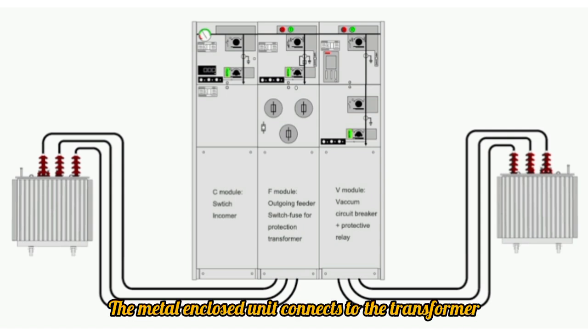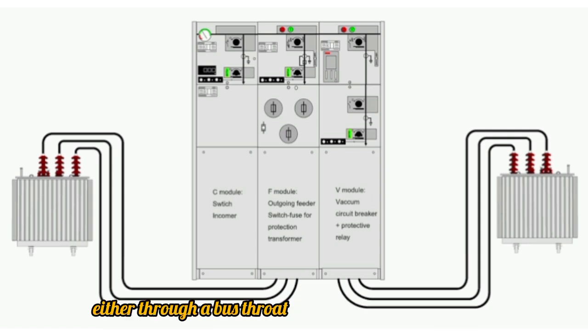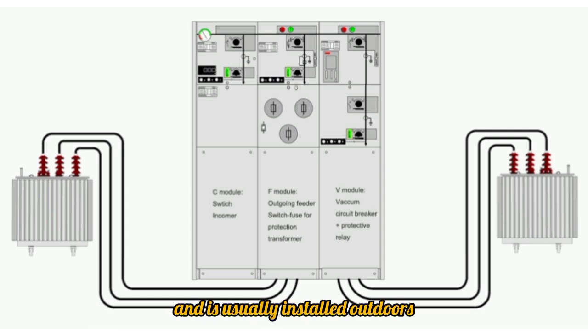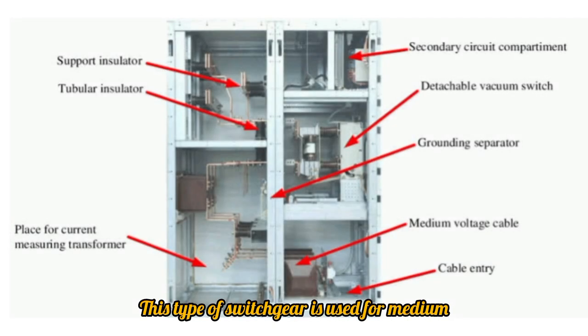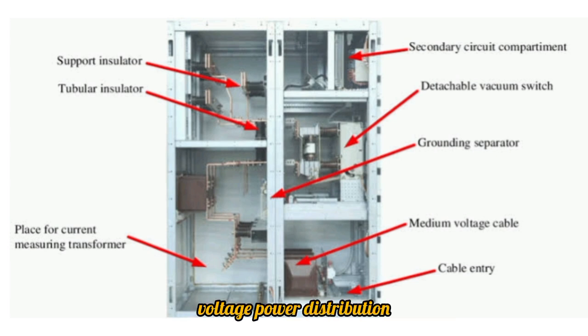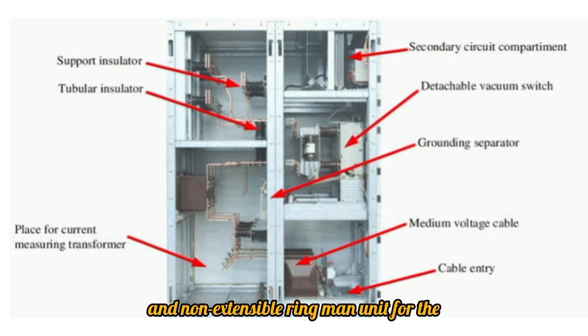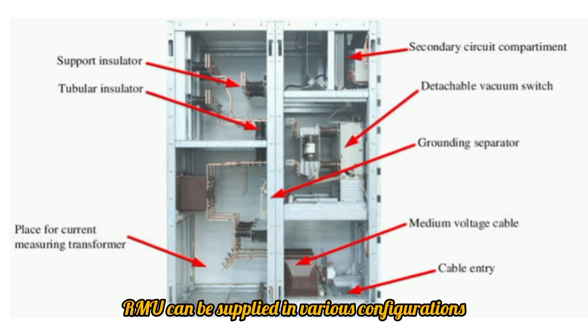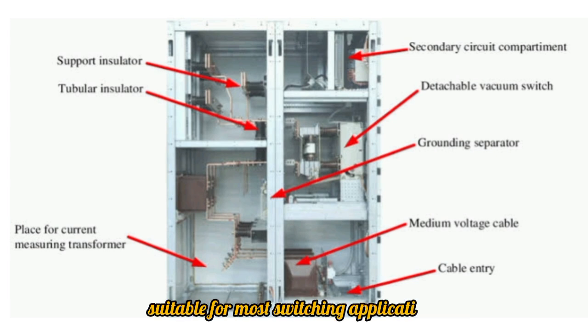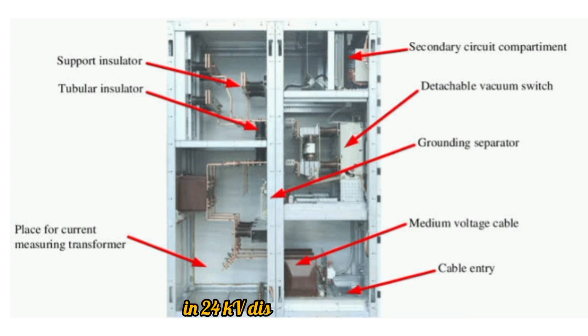The metal-enclosed unit connects to the transformer either through a bus throat of standardized dimensions or through cables and is usually installed outdoors. Ring main cables enter and leave the cabinet. This type of switchgear is used for medium voltage power distribution. RMU is an extensible and non-extensible ring main unit for the secondary distribution network. RMU can be supplied in various configurations suitable for most switching applications in 24 kV distribution networks.